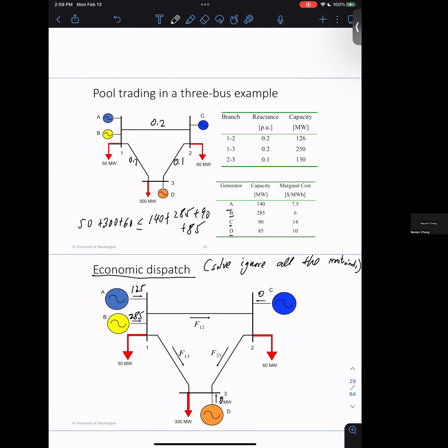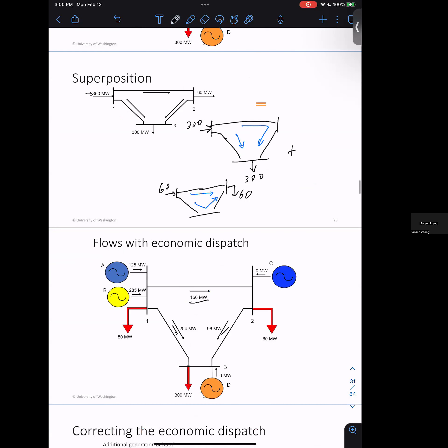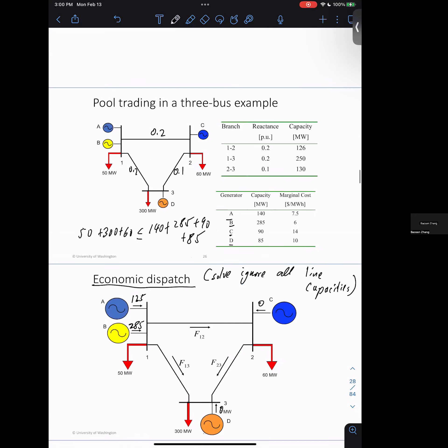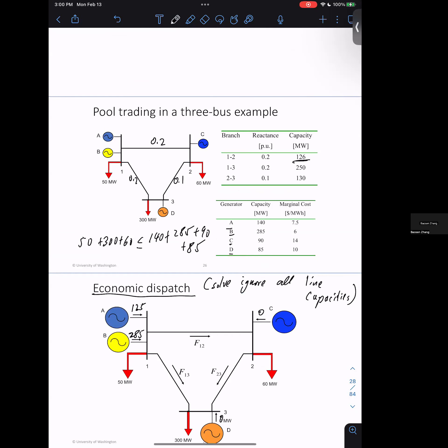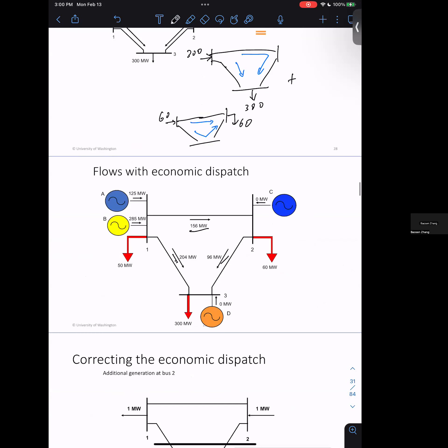This is the flow in the system if you ignore all line flow capacities. For economic dispatch, you ignore all line capacities — but this result is not feasible, because the line capacity from bus 1 to bus 2 is 126 MW, and here you have 156 MW flowing. So you're flowing too much power on this line and need to correct for it by reducing this flow.